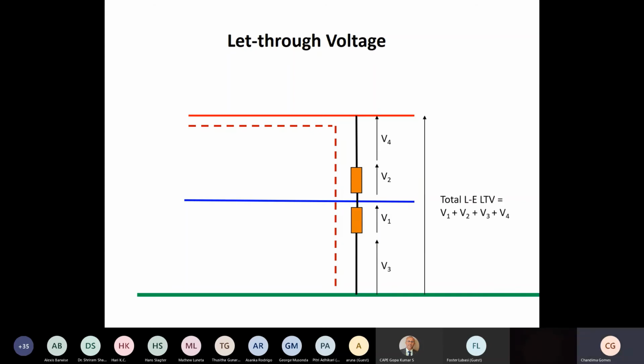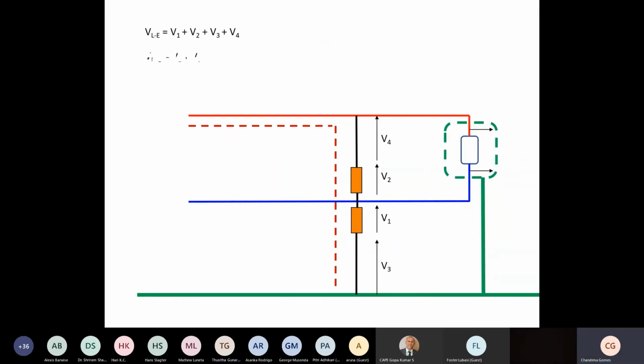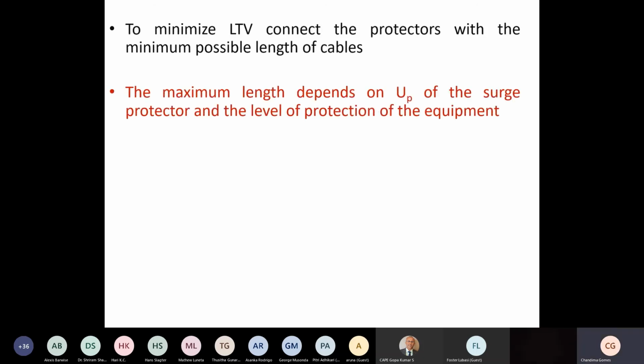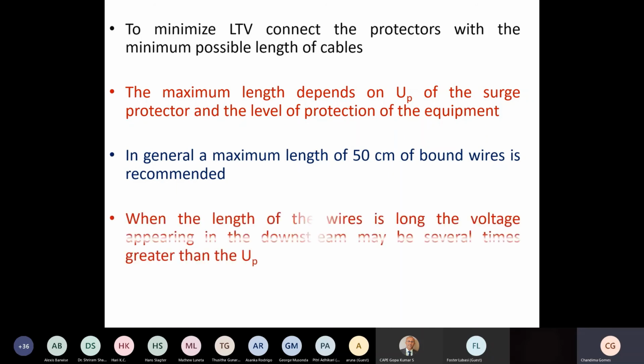So the total voltage will be V1 plus V2 plus V3 plus V4, where V1 and V2 are the UP values of the SPDs. So finally, what we see is these types of voltage differences between line and earth, neutral and earth, and line and neutral. So your equipment impulse withstand voltage should be covered by this, should be more than these voltages. Okay. So in order to minimize the let-through voltage, you should have cables as short as possible, usually 50 centimeters.